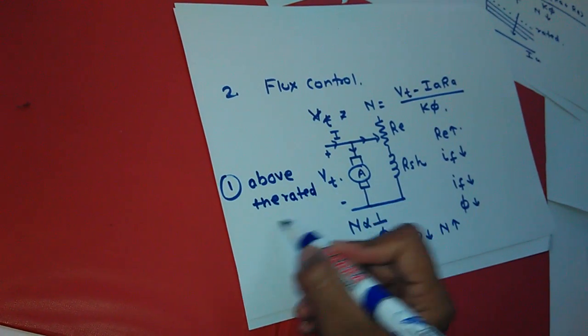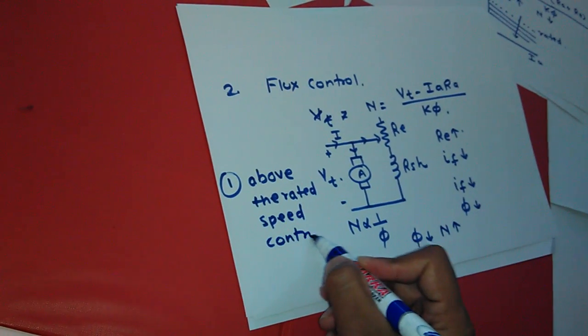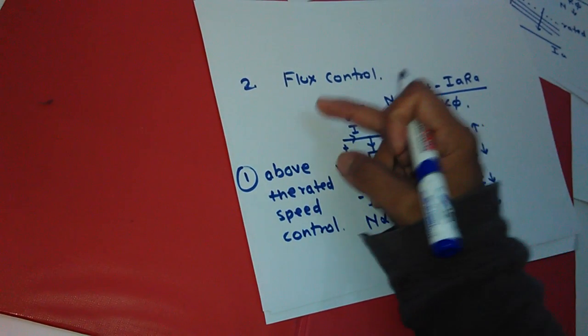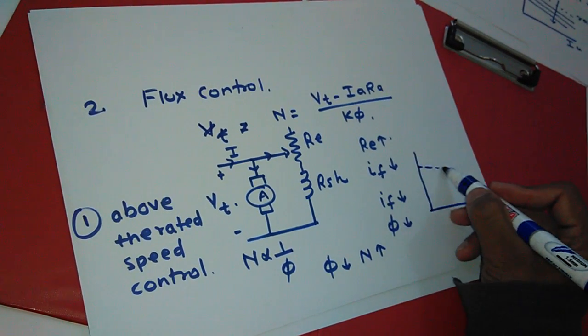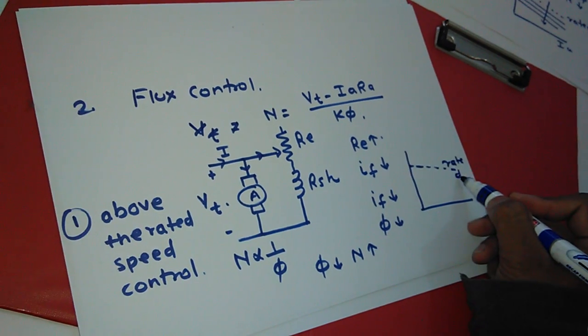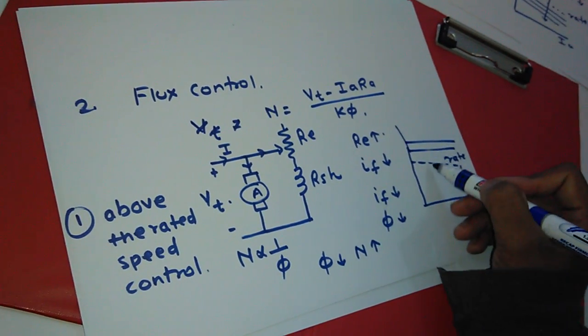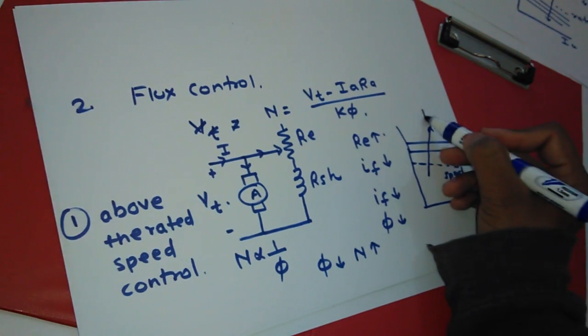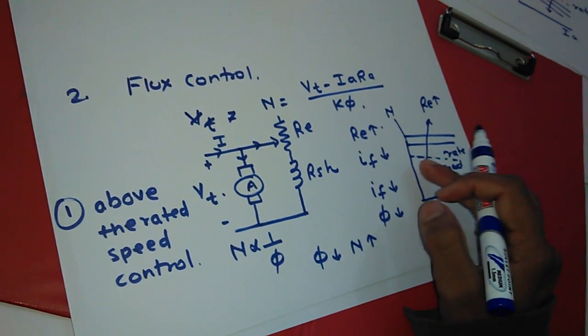The advantage is that above the rated speed, speed control is possible, and armature power loss is less — only losses take place in the field winding. So this is used for a wide range where speed is required to change above the rated speed. For the characteristic, the rated speed characteristic is shown, and we can get more speed beyond the rated speed by increasing the resistance.